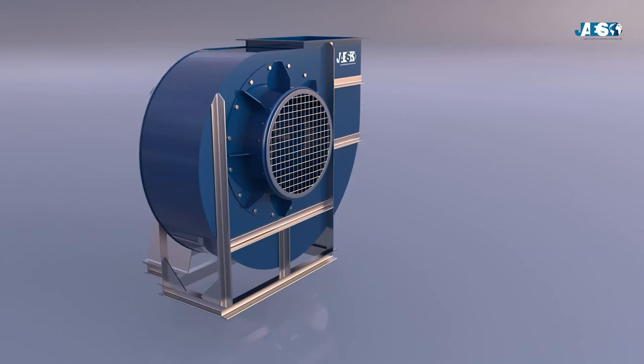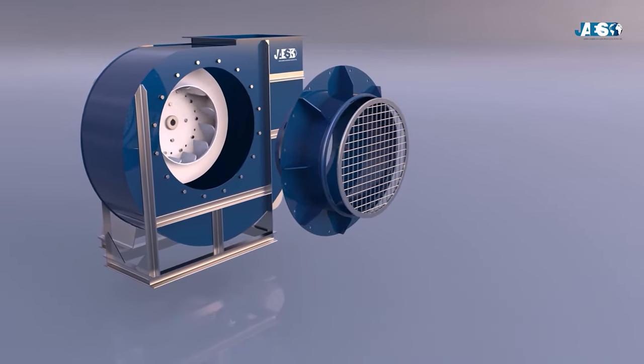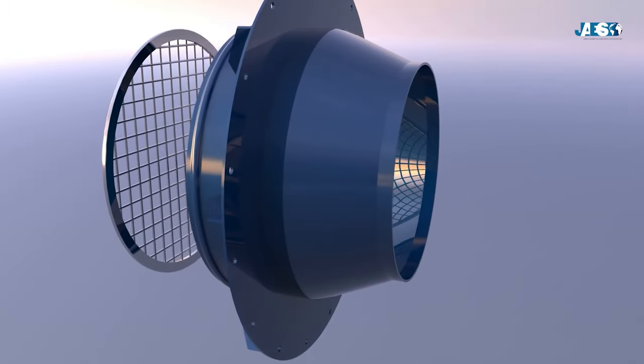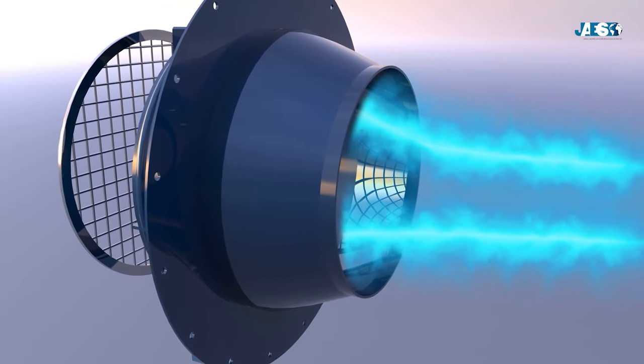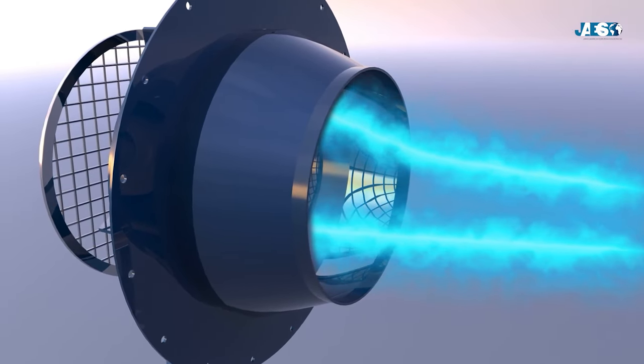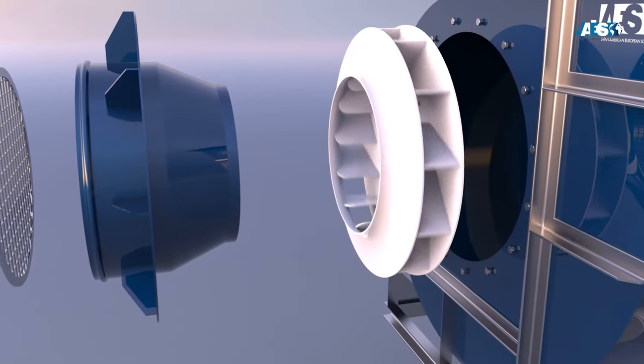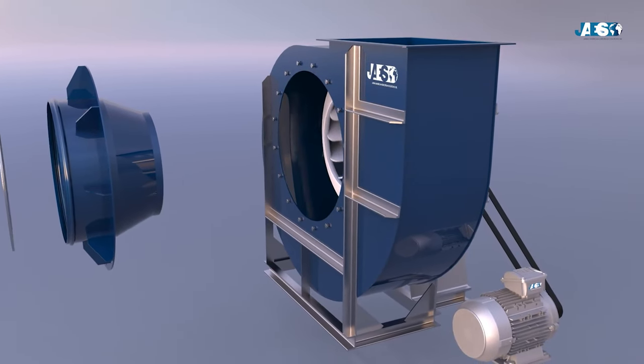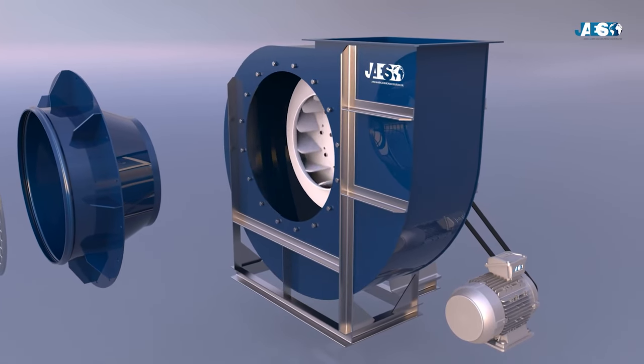If we observe its components, we'll find the inlet flange, which always integrates a protective grate, the inlet cone designed as a venturi tube to increase the speed of entry flow. Then we find the impeller, located inside of a snail-shaped structure in sheet metal. This design increases the centrifugal factor.